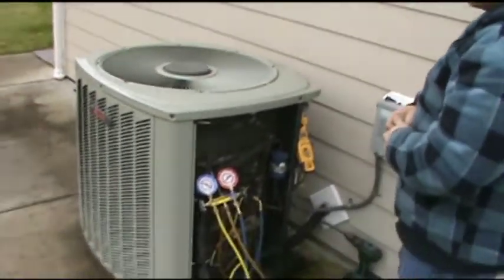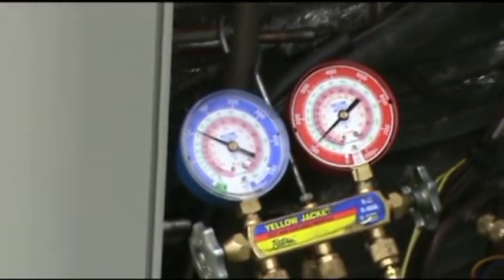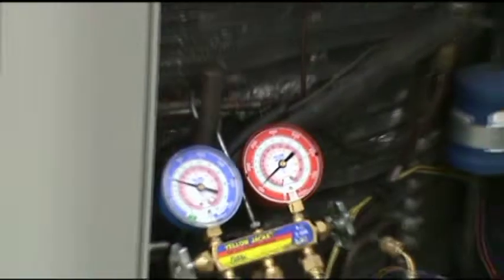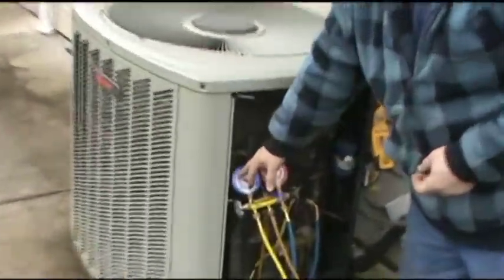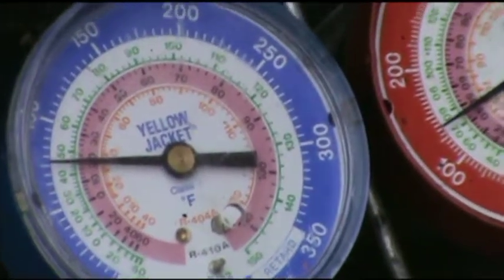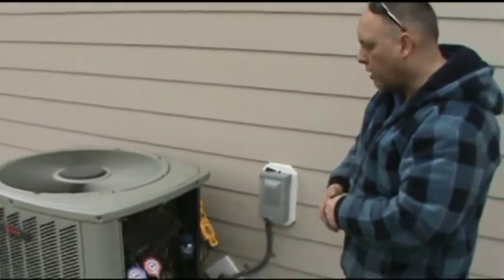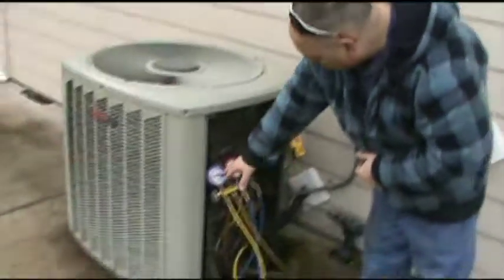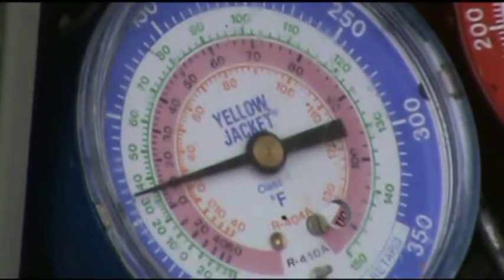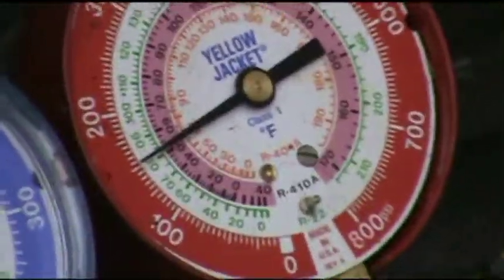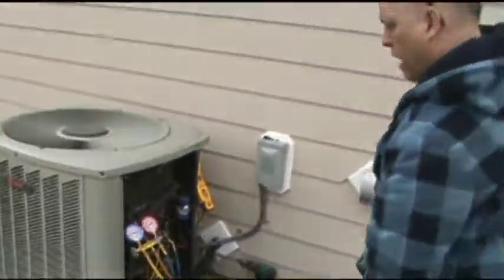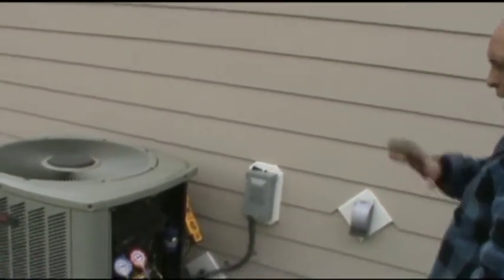The reversing valve changed. Condenser fan turned off, and we're actually running in air conditioning mode. We're going to see this drop to somewhere down around 50, and this is going to build and continue to build until the sensors that we check the values on read a certain temperature on the coil, and then it'll reverse it and put it back into heating mode. So we're down around 55 on the suction. Our high side pressure is at 150 and climbing. And it'll continue to run in this mode for up to 10 minutes. But here, since we have no ice on it, it'll probably terminate rather quickly and go back to regular heating mode.